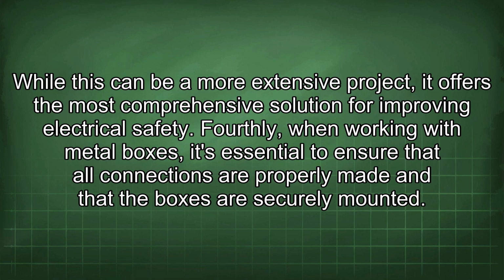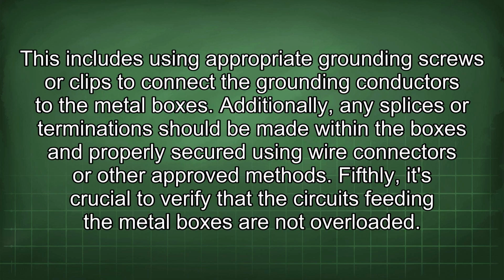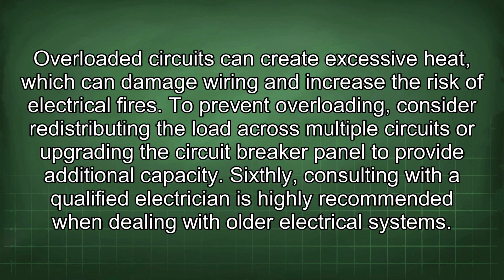Fourthly, when working with metal boxes, it's essential to ensure that all connections are properly made and that the boxes are securely mounted. This includes using appropriate grounding screws or clips to connect the grounding conductors to the metal boxes. Additionally, any splices or terminations should be made within the boxes and properly secured using wire connectors or other approved methods. Fifthly, it's crucial to verify that the circuits feeding the metal boxes are not overloaded. Overloaded circuits can create excessive heat, which can damage wiring and increase the risk of electrical fires. To prevent overloading, consider redistributing the load across multiple circuits or upgrading the circuit breaker panel to provide additional capacity.